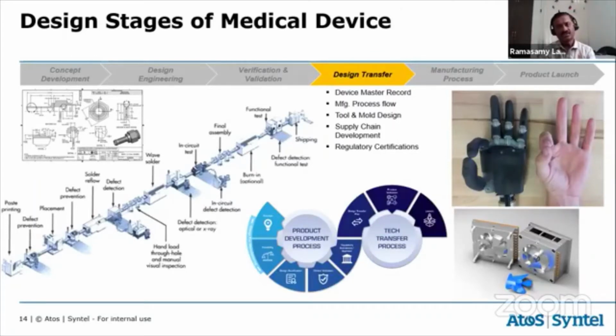If we create a new type of screw, not every screwdriver will open it, so we would have to supply a special purpose screwdriver, which is not required. So we have to standardize everything. And the inside part should be accessible through a small hole, otherwise the service person may have to open the whole device. This is called design for service. And then design for assembly: in the manufacturing process, the assembly should also be proper. There are a lot of design considerations: design for manufacture, design for assembly, design for shipment, and so on. This is called the design transfer phase.